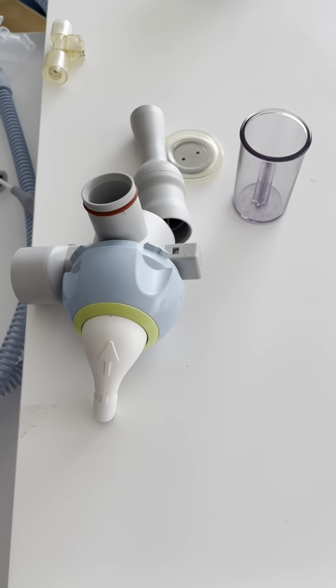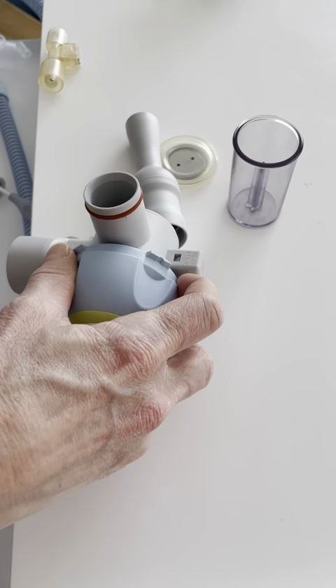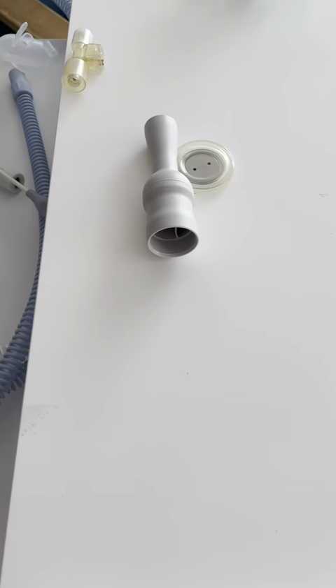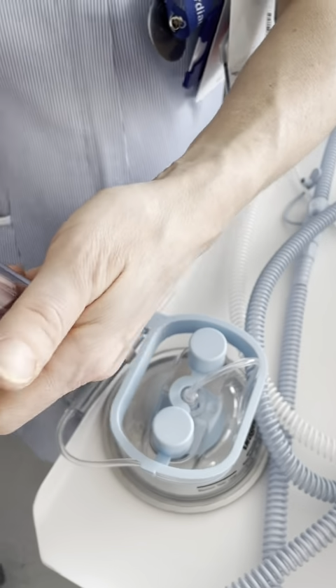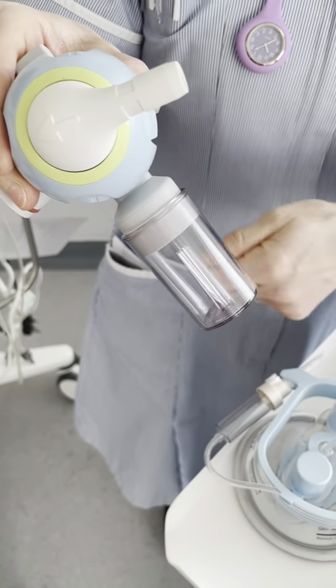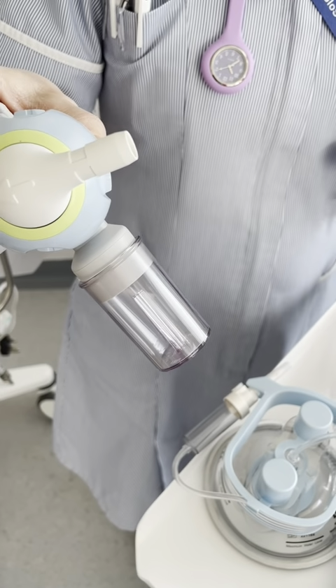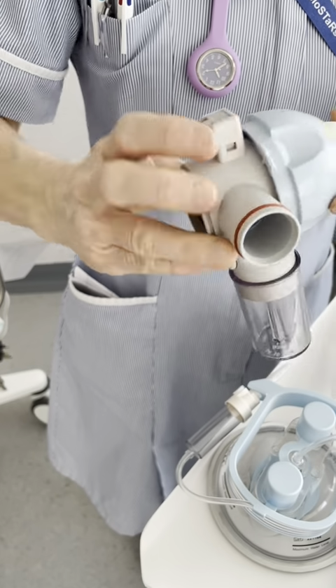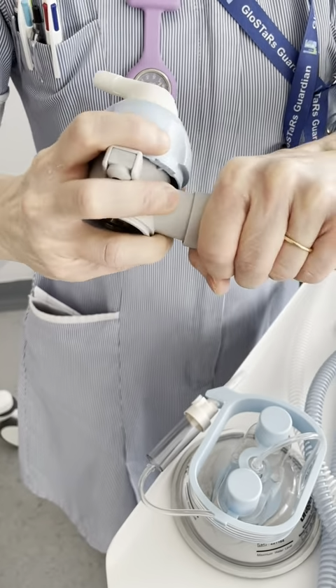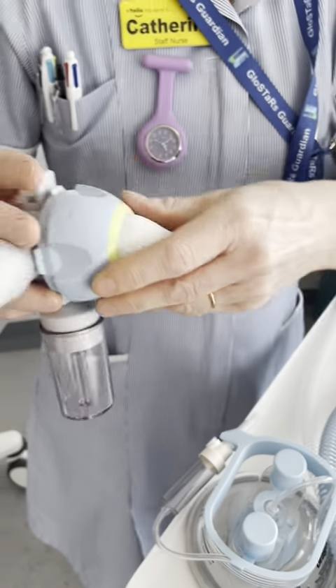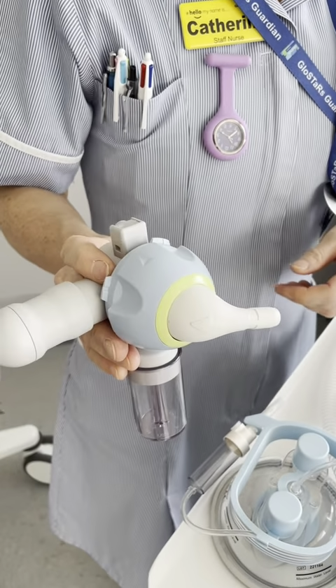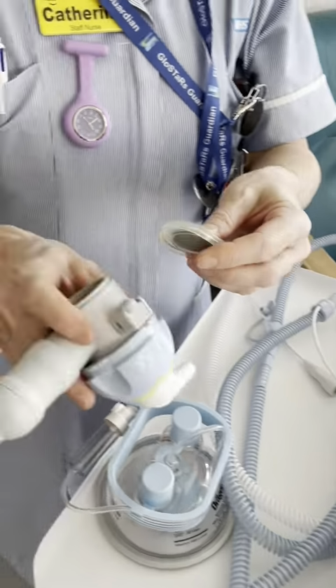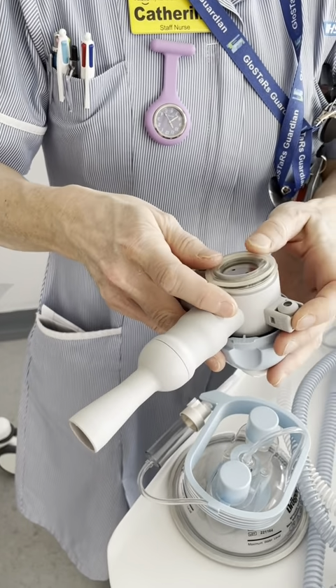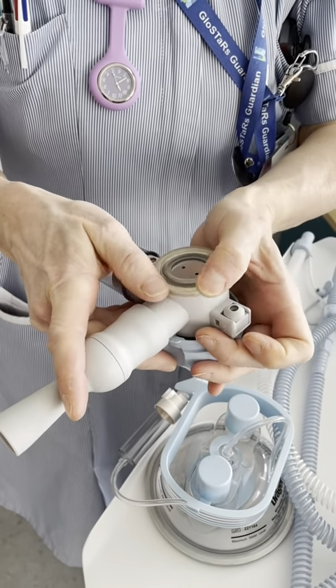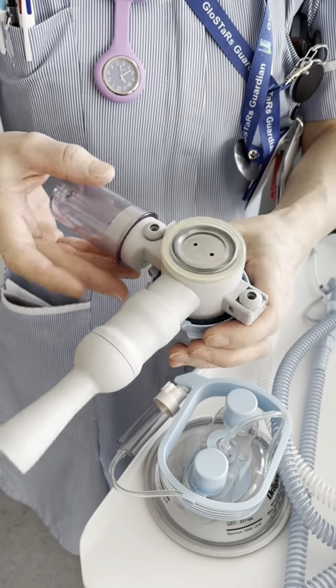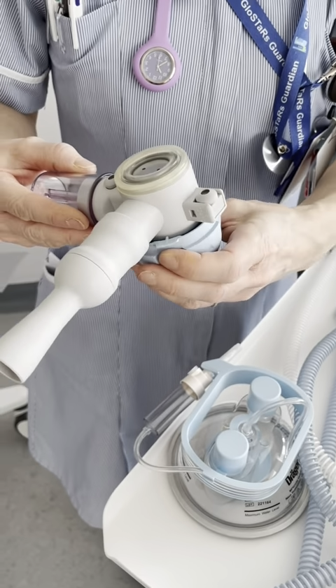The Draeger ventilator expiratory set comes in a pack from CSSD. In order to assemble, attach the nebulizer pot, the exhaust, and then finally the diaphragm, which sits onto the block like a hat. This block is then ready to insert into the expiratory port.